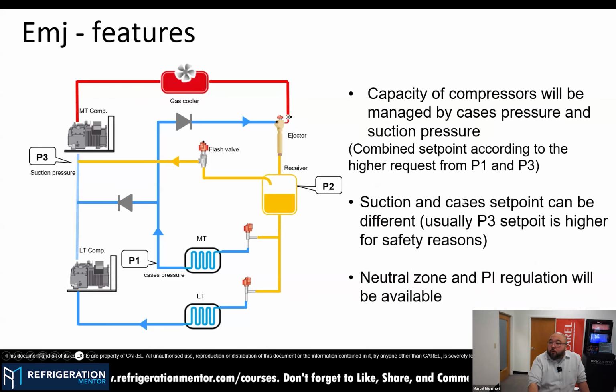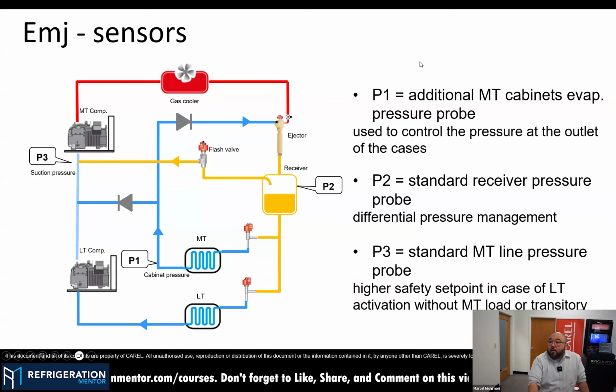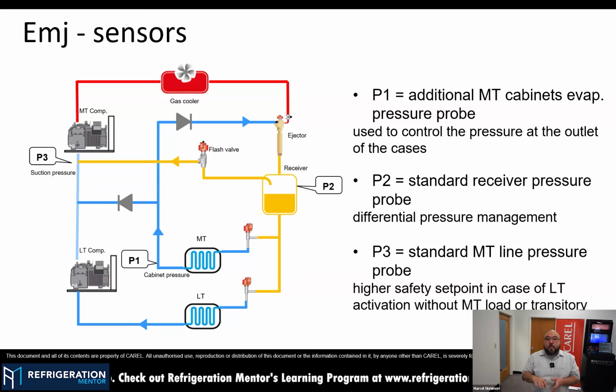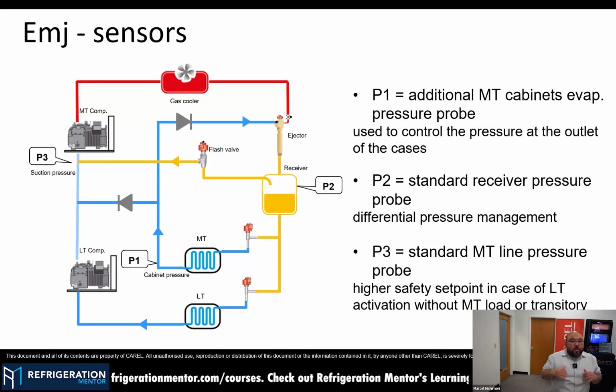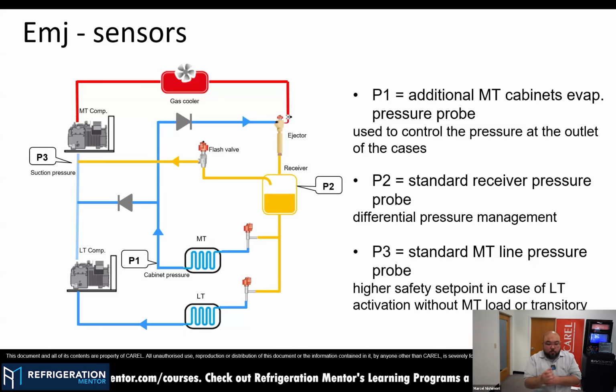So, the standard MT pressure probe, the P3, and the P1, the additional pressure probe that we will add. You'll see I'm adding more efficiency to the system, with less complexity on the mechanical side and less complexity on the electronic side. It's just one pressure probe that we are adding. From the case perspective, you could have any controller in the case; you don't mandatorily need to have it connected. If you have it connected, we can have better efficiency and better performance, but it's not mandatory. You could have it connected to CAREL controls or to third-party controls. We are really flexible in the way we control things, so we can provide maximum flexibility to our customers.